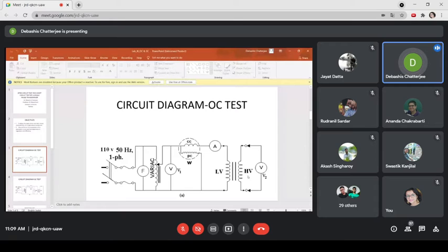For 100 volt it is very easy. We can have a variac and just apply the voltage. So this is another issue. Second, the wattmeter. If we connect at the high voltage side, its potential coil should be rated at least 1 kilovolt, since it has to face 625 volt, as we just saw.